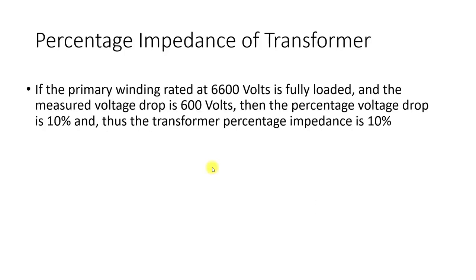On this distribution transformer nameplate, the percentage impedance is six point zero four percent. You will observe that as the voltage level increases, the percentage impedance also keeps increasing. For example, if a transformer has a rated winding voltage of 6600 volts at the primary side and the voltage drop at full load current is 600 volts, then the percentage voltage drop is 10 percent — so the percentage impedance of that transformer is 10 percent.